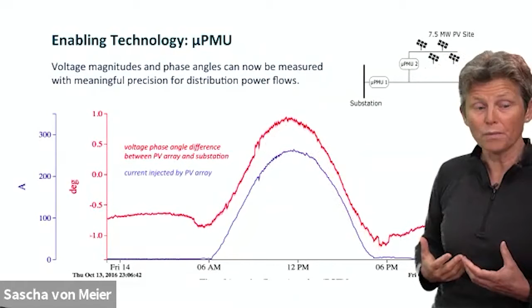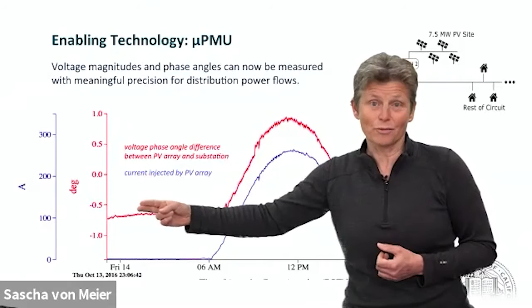And then in red, you're seeing the voltage phase angle difference, that is the phase shift between MicroPMUs 1 and 2. And you see here, this goes from -0.5 degree to +1 degree. This is mixed in with load. So really, the phasor difference is showing kind of a net power flow on this line, and we don't have measurements in this picture from the load, but the solar generation is kind of dominating this picture. And so you can see very well how the phase angle difference correlates with the power flow, and also the fact that you need to make some really precise measurements to get any information out of this.